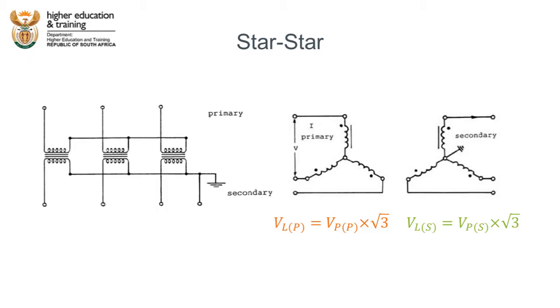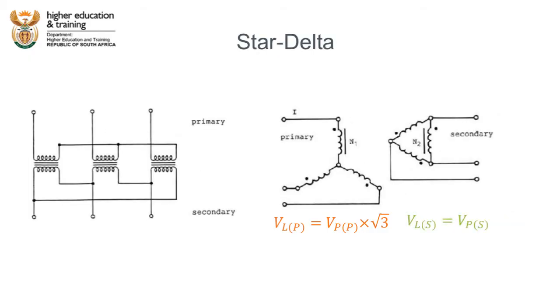We can also connect the transformer as a star-delta. In this instance, the primary side is connected in a star formation and the secondary side is connected in a delta formation. On the primary side, the line voltage equals the phase voltage multiplied by the square root of three. On the secondary side, the line voltage equals the phase voltage, because the secondary side is connected in a delta configuration.